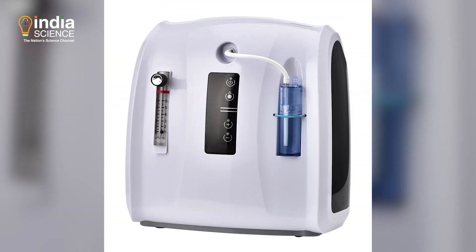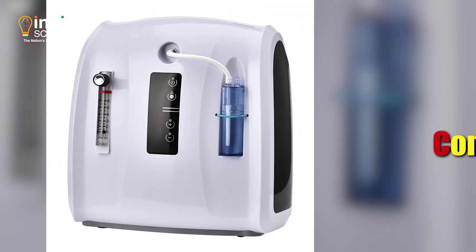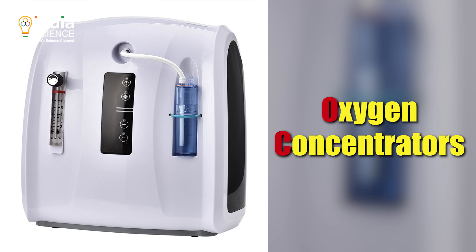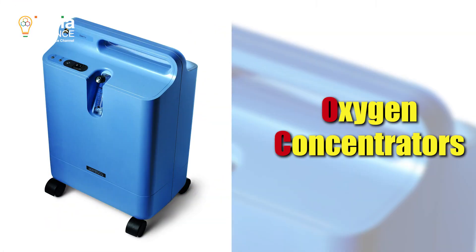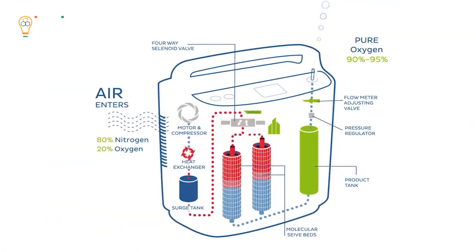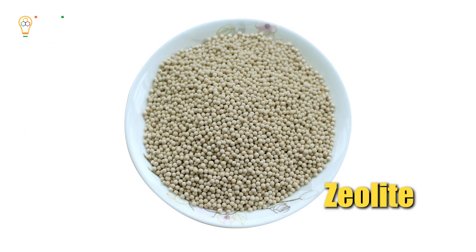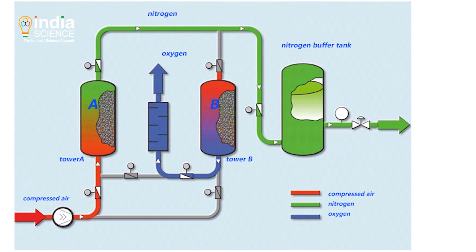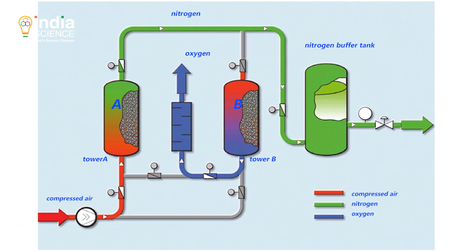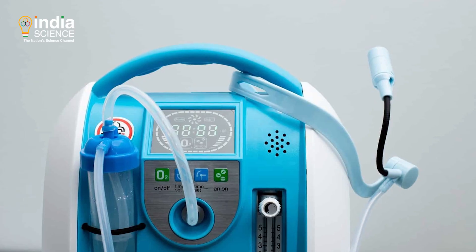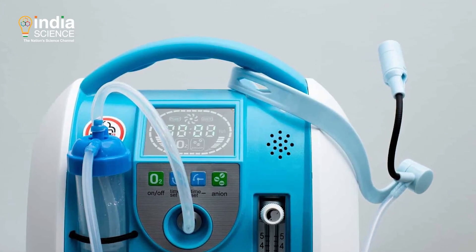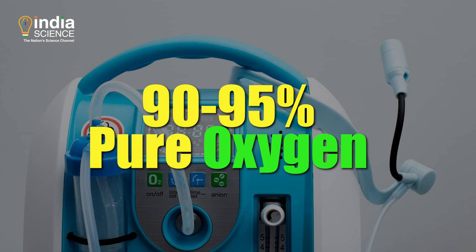There are portable oxygen generators as well, known as oxygen concentrators. These can be used at home. In this, the air is compressed using compressors and then sent to sieve beds. In sieve beds, there is a compound called zeolite, which separates the nitrogen from oxygen. This leads to the generation of pure oxygen, and the resultant air is 90 to 95 percent pure.